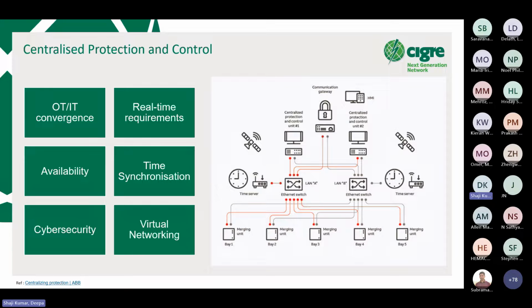This free allocation of functions, and provision of functions from various providers independent of hardware, allows implementations with different granularity. But it needs to be ensured that the chosen granularity matches required performance and reliability requirements, like availability and time synchronization requirements, or performance requirements derived from 61850-5, specific to protection and control functions. All software must comply with specified levels of cybersecurity requirements. In the end, the selection and dimensioning of the right hardware platform plays a major role in virtualization, redundancy, and cost considerations.